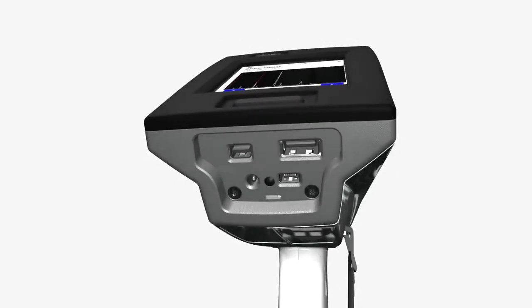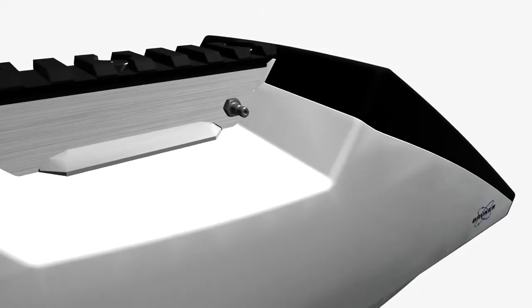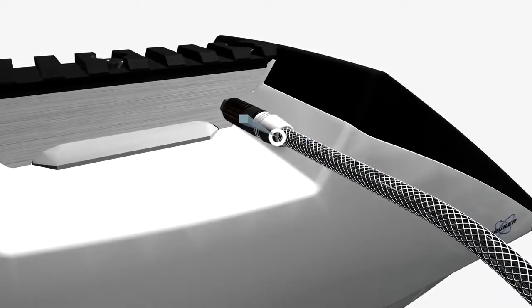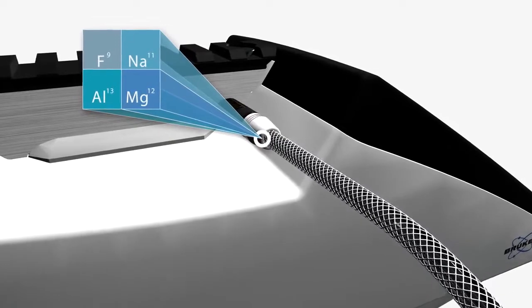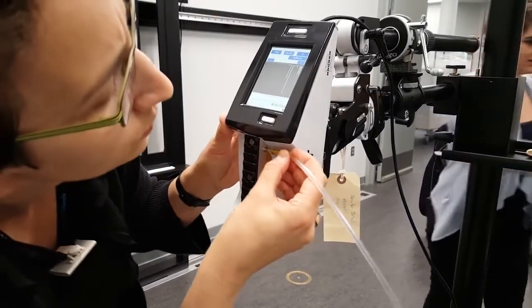Its integrated Wi-Fi and Bluetooth allow connectivity where and when it's needed. Our Tracer 5i provides the capability of a vacuum, helium, or air beam path for analytical optimization of elements as light as sodium or as heavy as uranium in simple or complex matrices.